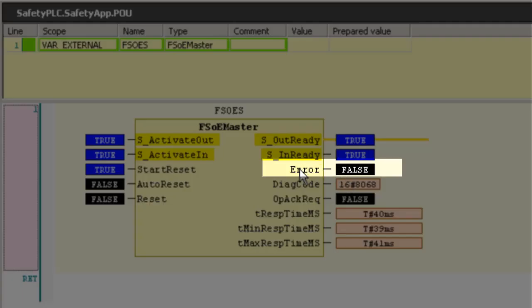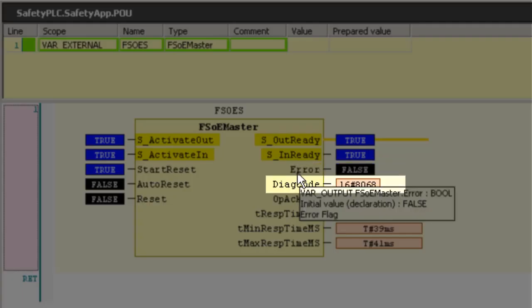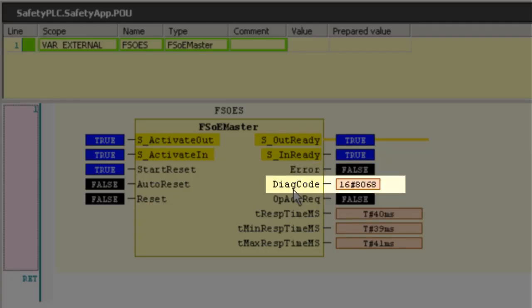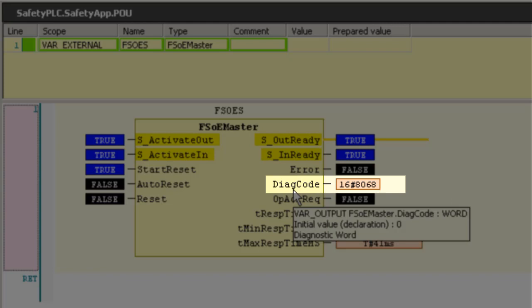All safety related function blocks have two error related outputs. Error and the DIAG code. In DIAG code we see the status of the safety I/O. The high byte is HEX 80. That means there is no error. The low byte is HEX 68. That means that process data are transmitted.